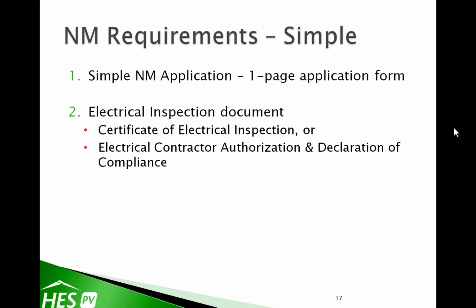To get accepted for connection to the grid, we require you or your electrician to produce an electrical inspection document. Two types of documents are acceptable: either a certificate of electrical inspection issued by an inspector if they choose to come and inspect the project, or, if your electrician is an FSR, field safety representative with the BC Safety Authority, they can issue their form, I believe it's form 206, called Electrical Contractor Authorization and Declaration of Compliance. Either document is acceptable. If your electrician uses an online system, they can PDF either document and email it to me. That's acceptable.